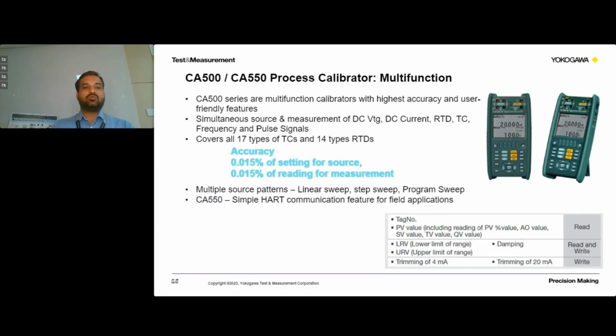In this, we have one more model called CA550. It is a simple HART communication feature added for this particular calibrator, where we will be able to do some basic HART communication functions in the field, such as reading of the tag number and checking the primary value, secondary value, those kinds of things. And we will be able to read and write both lower range value and upper range value, and we will be able to change the damping constant.